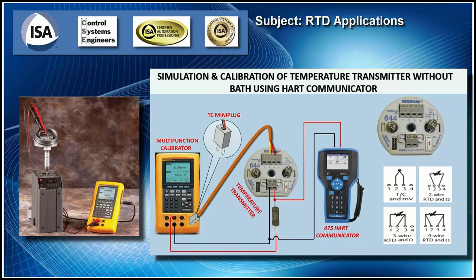The best way to do this, though, is to actually have the element. The wires come up through the center of the disc right there, a puck or a disc, and the wires come up and connect in. And then, as you see here on the left, it sits in the top of the housing. And then you put the stem, the sheathing, down inside what they call a hot box or a metrology well. A lot of times these are referred to as a temperature bath. And typically these boxes will do refrigeration and heating. A typical Fluke may go to minus 45 C and up to 700 C.